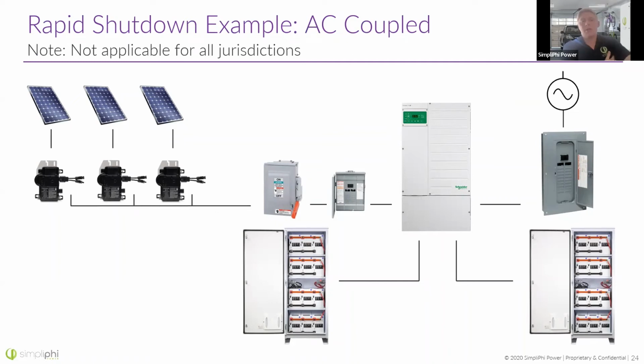Now, one thing to note is that if you've got an AC coupled system and let's say you don't need that rapid shutdown single button, then you can probably just get away with a disconnect here, just a PV array disconnect.